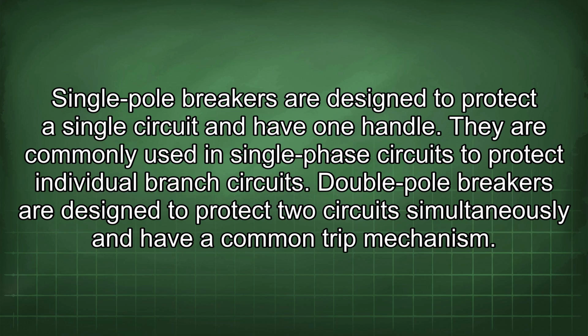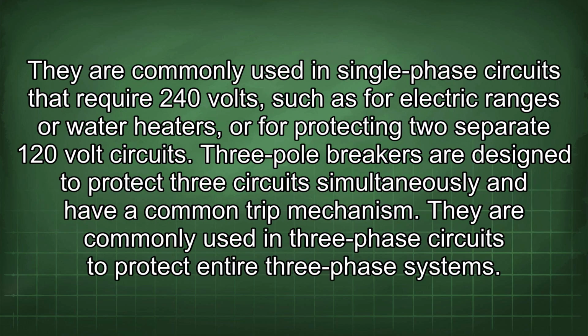Single-pole breakers are designed to protect a single circuit and have one handle. They are commonly used in single-phase circuits to protect individual branch circuits. Double-pole breakers are designed to protect 2 circuits simultaneously and have a common trip mechanism. They are commonly used in single-phase circuits that require 240 volts, such as for electric ranges or water heaters, or for protecting 2 separate 120-volt circuits. 3-pole breakers are designed to protect 3 circuits simultaneously and have a common trip mechanism. They are commonly used in 3-phase circuits to protect entire 3-phase systems.